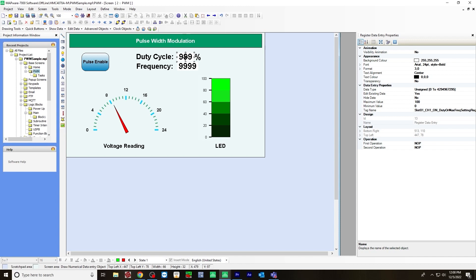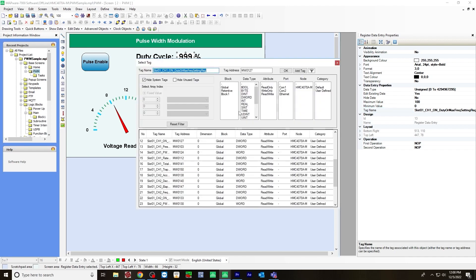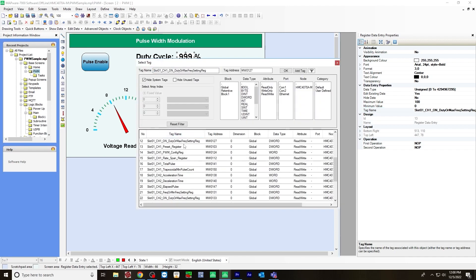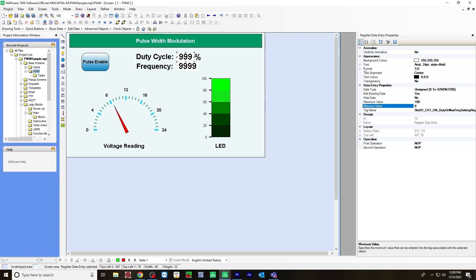So I'll show you how to adjust the properties on the right over here. First, I assigned it a tag name. So for the duty cycle, I'm going to use slot one channel one on duty or max frequency setting register. And you do that by finding it here in the tag names. So this one right here you'd use. And for a maximum value, I put 100 for minimum zero. And I also changed the format to have three digits and zero digits after decimal point.